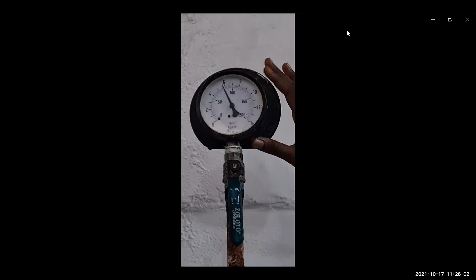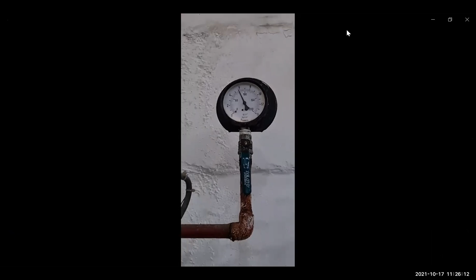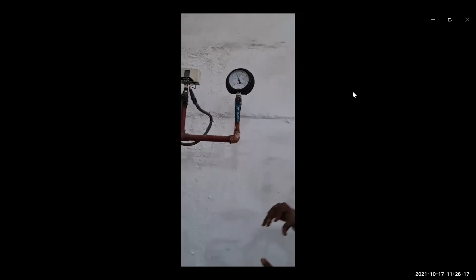Now this equipment is called a pressure gauge. As I told you, in the water pipeline the water is fully charged or pressurized. So this pressure gauge will tell us what the pressure in the pipeline is. Now this entire system works in auto mode. What is auto mode? See, at the moment there is 6 kg pressure, you can zoom in and show. 6 kg pressure is maintained in the firefighting pipeline.